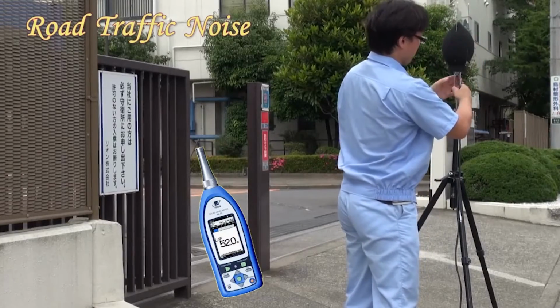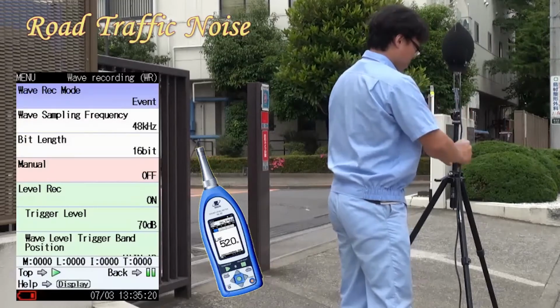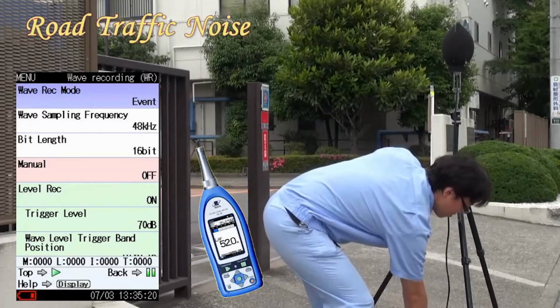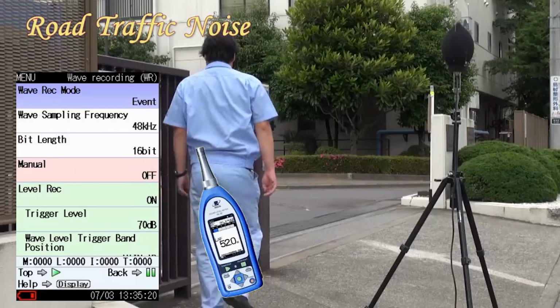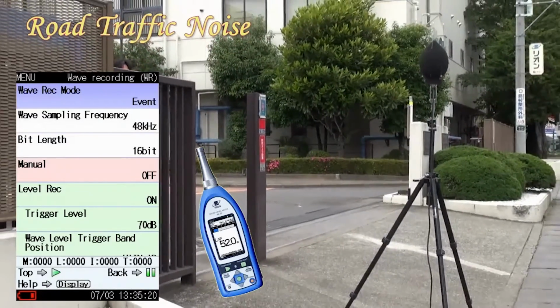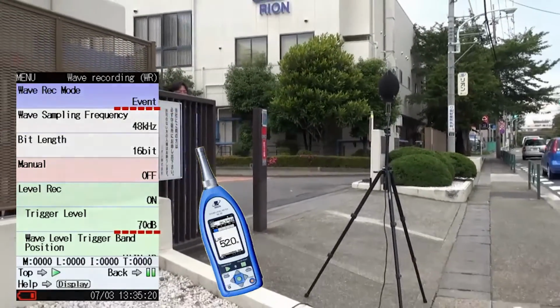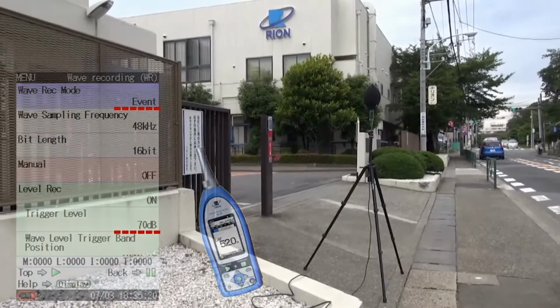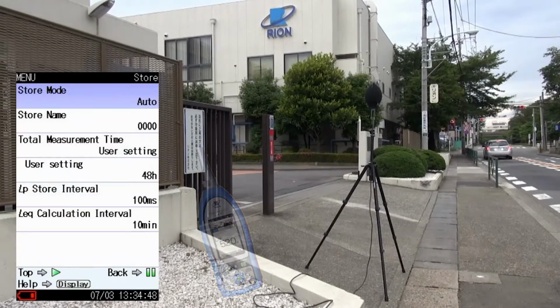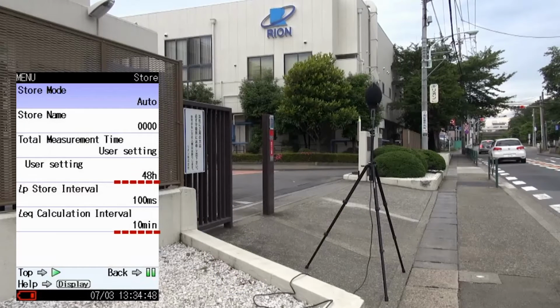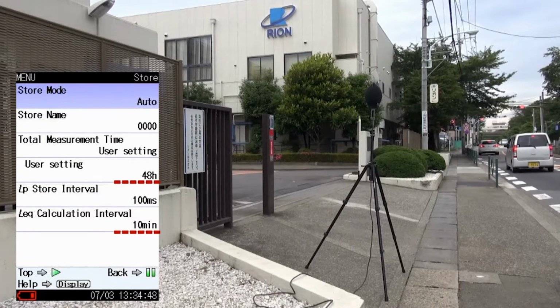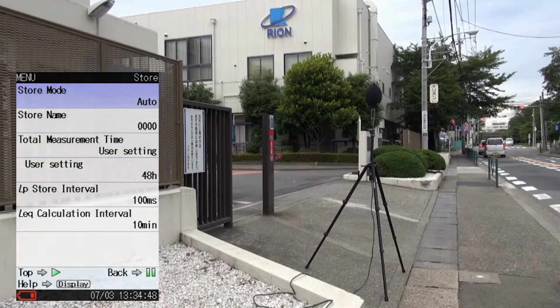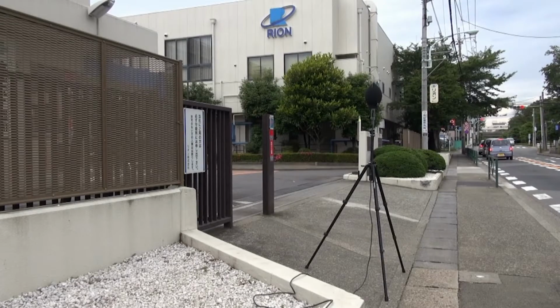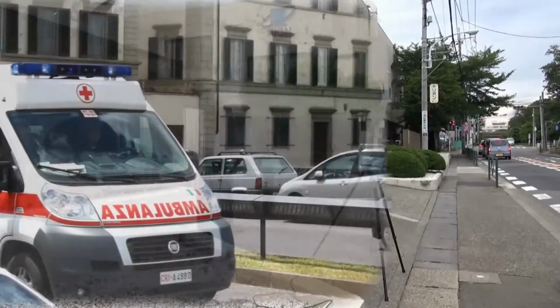Let's have a look at how the AS-60 program works using a 2-day observation of road traffic noise taken with the RION NL52 sound level meter. Using an NL52 event function, the event recording is for noise above 70 decibels. The road traffic noise has been stored as LEQ data at 10-minute intervals and as LP data for 2 days using the auto store mode. To properly evaluate road traffic noise, unnecessary sounds like the loud noise of an ambulance passing by should be excluded from the LAEQ calculation.